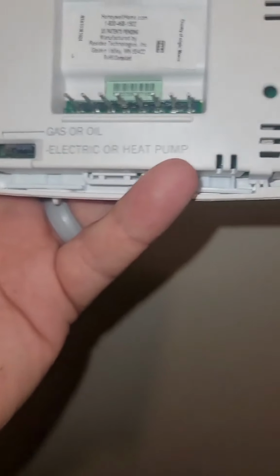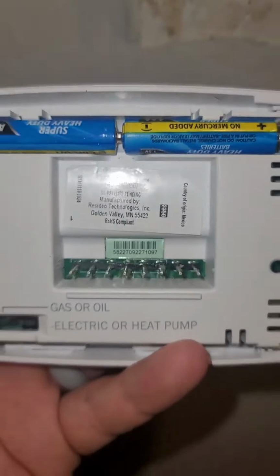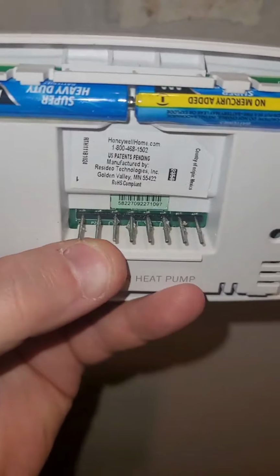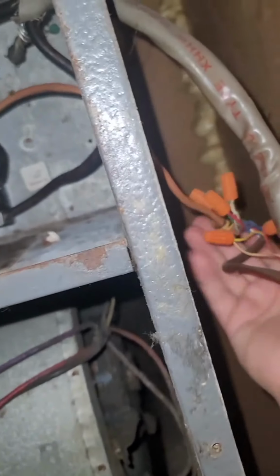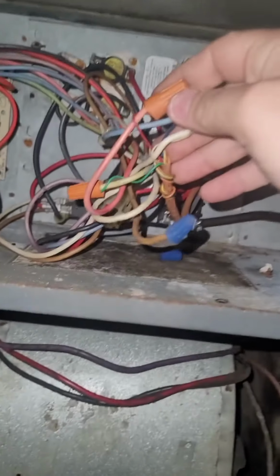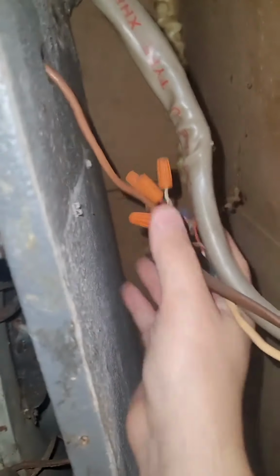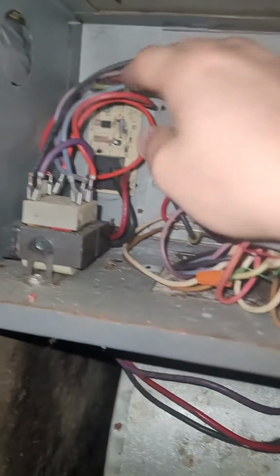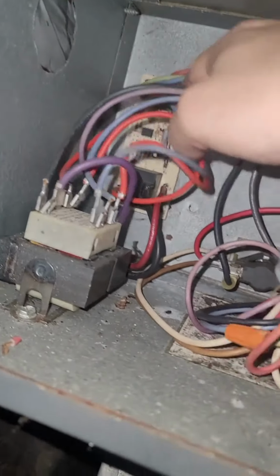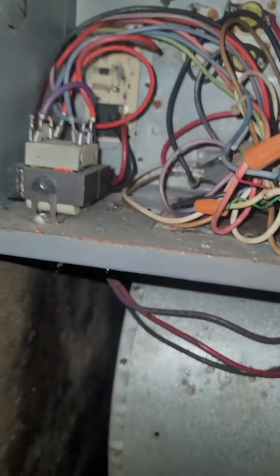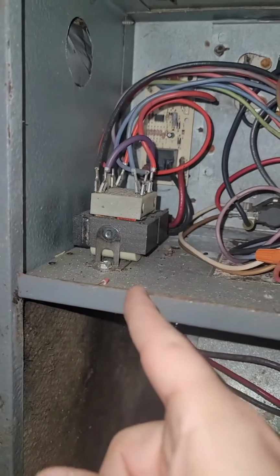We also want to make sure we got it on electric, because this is an electric heat, and we want to make sure those pins aren't bent. Sometimes those pins can be bent and it's just overlooked, so we just want to be really detailed about it. Snap it back in place, and let's go back toward the air handler. So we got that part taken care of. We always want to look at all these little wire nuts. Sometimes they don't have good connections, and that could cause it not to heat or cool, the fan not to come on, etc. Checking the board out, looking at all this stuff, just making sure.